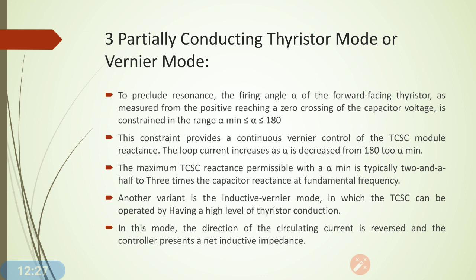To save the TCSC from the resonance condition, the firing angle alpha of the forward-facing thyristor, measured from the positive zero crossing of the capacitor voltage, is constrained in the range of alpha minimum to 180 degrees. This provides continuous vernier control of the TCSC module reactance. With a decrease in the value of alpha, the loop current increases. The maximum TCSC reactance at alpha minimum is typically two and a half to three times the capacitor reactance at fundamental frequency.